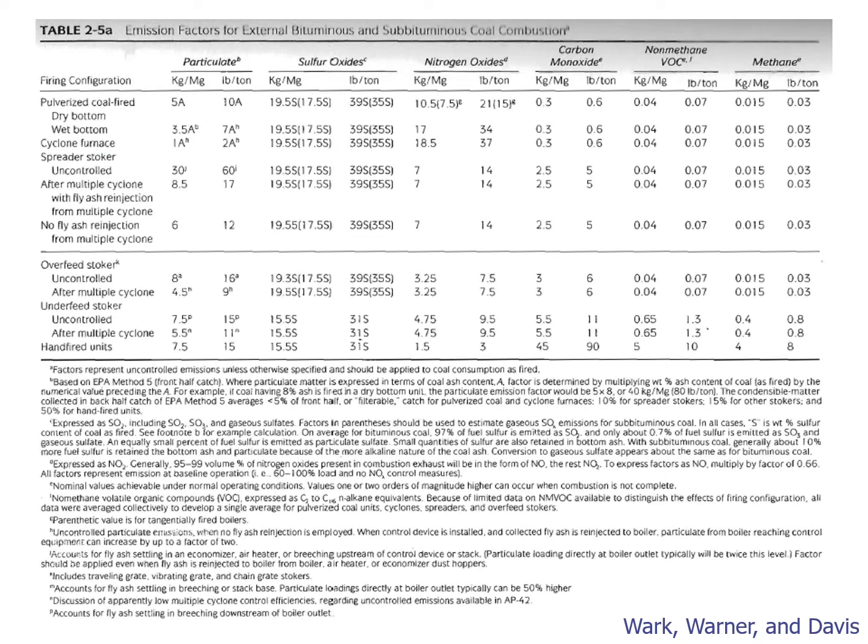This table shows an excerpt from AP-42, its emission factors for external bituminous and subbituminous coal combustion. So for example, I talked about a pulverized coal-fired boiler, and we were interested in figuring out the emission factor for sulfur oxides. I was doing this in units of pounds per ton. And you can see that for all these different pulverized coal-fired boilers, my emission factor is 39 times S. And if I go down and read the footnotes, I could see that the S stands for the weight percent of sulfur in the coal, and that sulfur oxides here is mainly SO2. If you look at the columns across the top here, there's also emission factors for particles, nitrogen oxides, carbon monoxide, non-methane volatile organic compounds, and then methane.